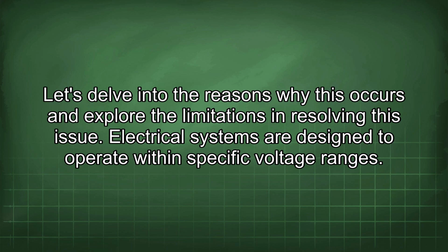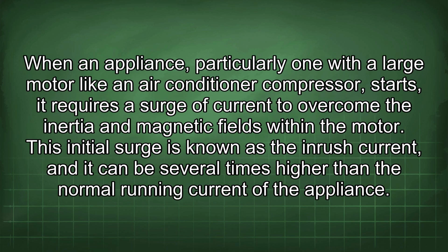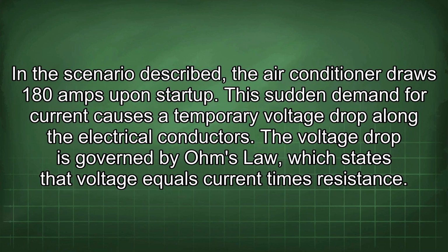Electrical systems are designed to operate within specific voltage ranges. When an appliance, particularly one with a large motor like an air conditioner compressor, starts, it requires a surge of current to overcome the inertia and magnetic fields within the motor. This initial surge is known as the inrush current, and it can be several times higher than the normal running current of the appliance. In the scenario described, the air conditioner draws 180 amps upon startup.